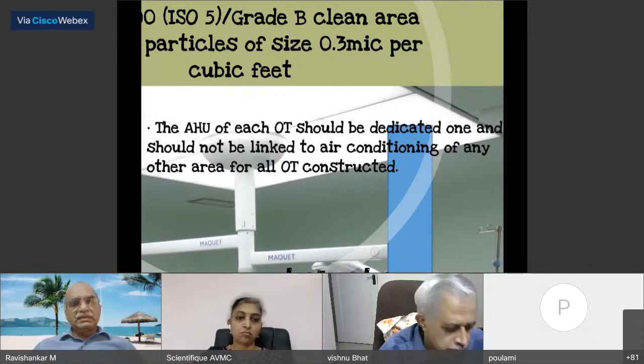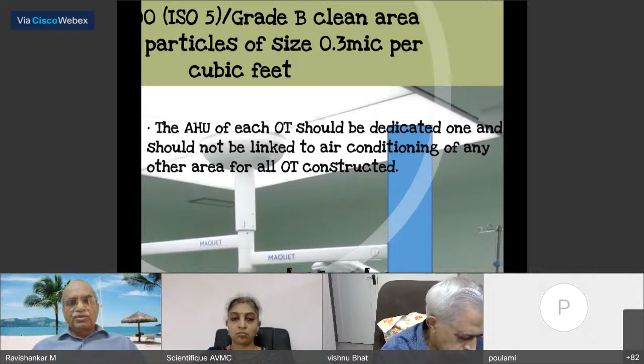Most important thing is the air handling unit for each of the OTs should be separate. It should be dedicated. It should not be connected to any other place, and there should not be any air returning back to this AHU from some other place. That is one of the most important things. You cannot have one air handling unit for two theaters distributing the air to both the places. It should be dedicated to one. And what do you do during the non-functional hours?